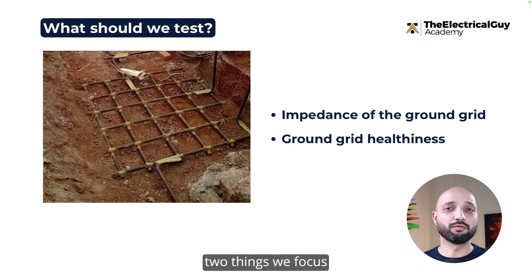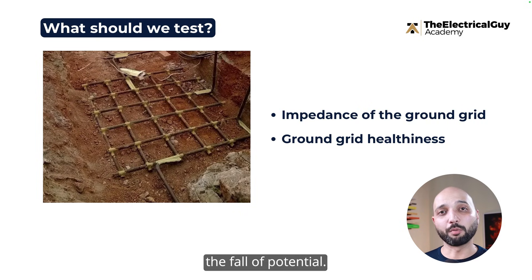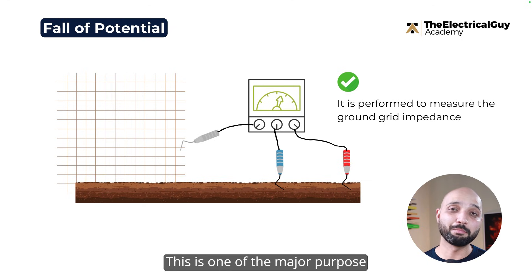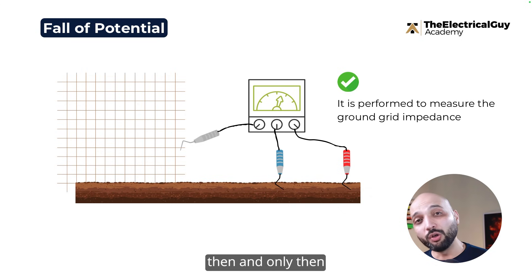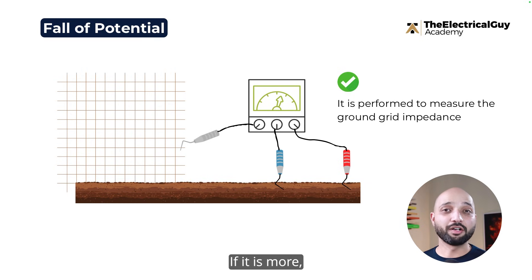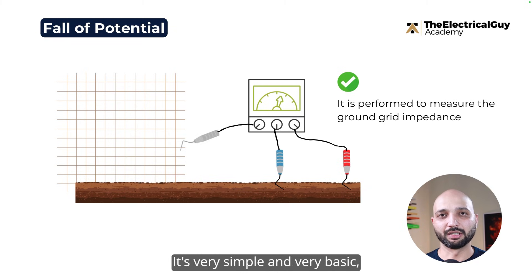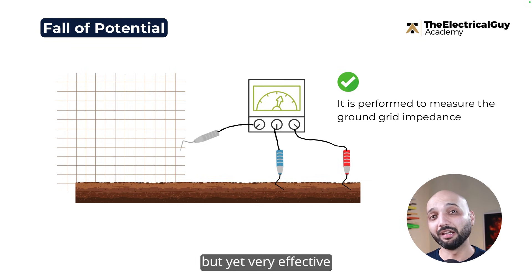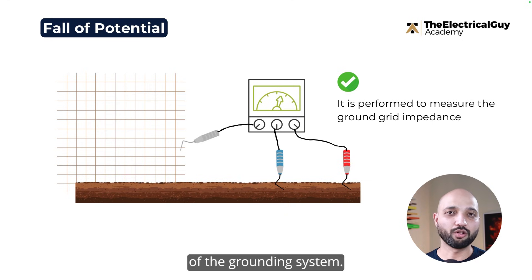The testing methods we'll see basically focus on these two things. We are testing the grounding system to ensure its impedance is low, because only then will the fault current pass through it. And second, we need to make sure the grid is healthy — that there are no broken points, loose connections, or corrosion. Fall of potential is used to test the impedance. It's a simple but very effective method used worldwide, and when the impedance is low, that means the system is healthy.